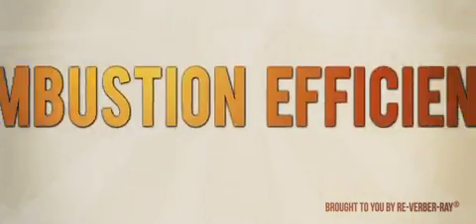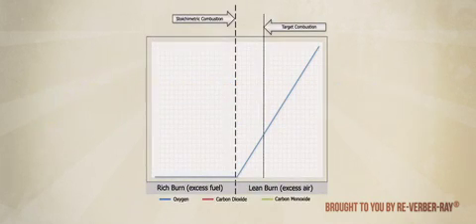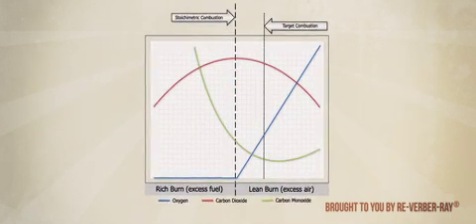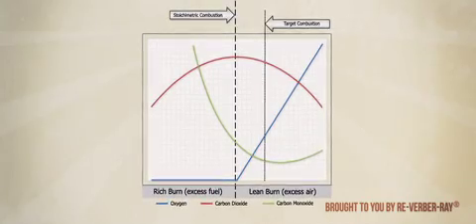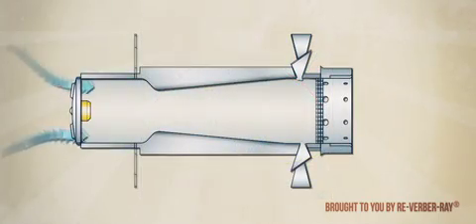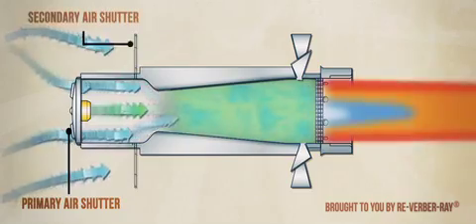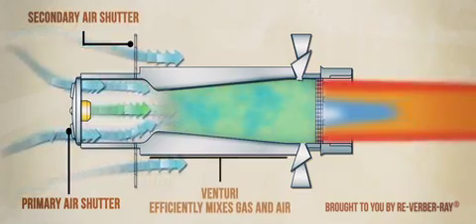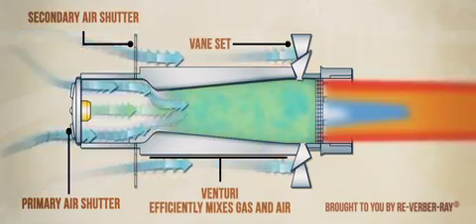Combustion efficiency is a measure of how completely an appliance converts the supplied fuel into heat energy. 100% combustion efficiency is achieved when the exact amount of oxygen required to burn a specific amount of fuel is supplied to the reaction.